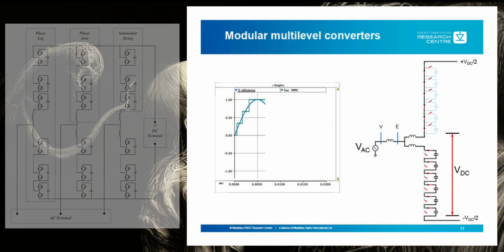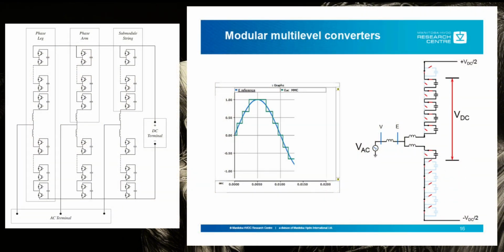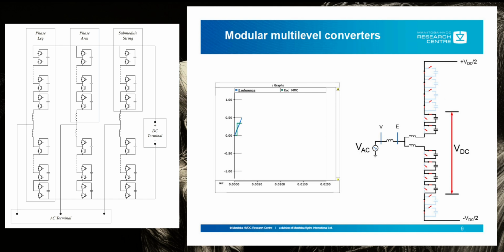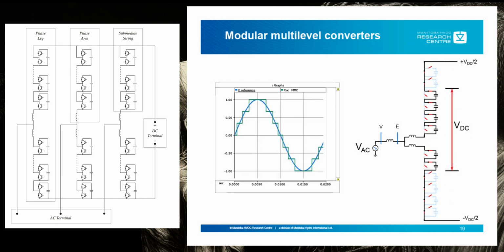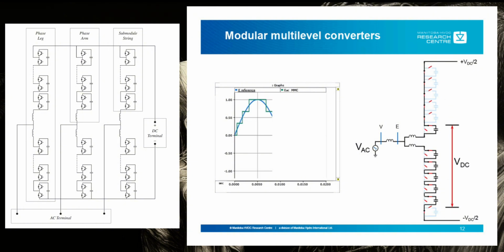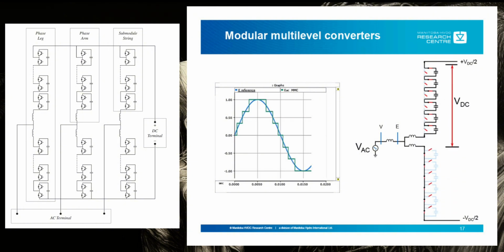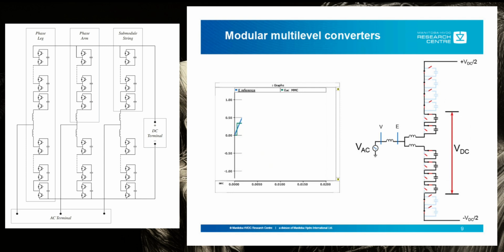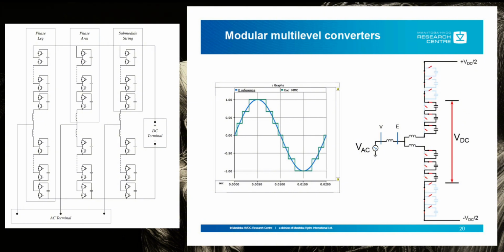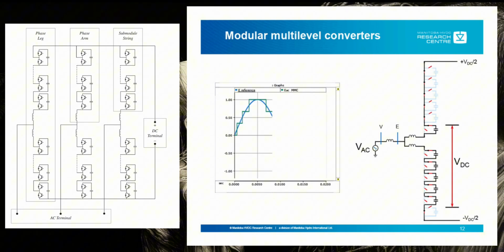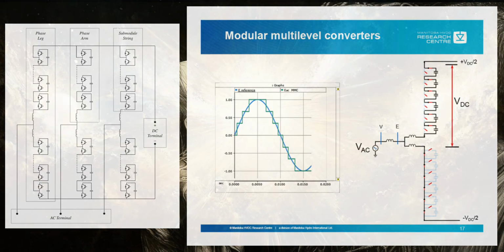While several converter topologies exist for voltage source converters, the modular multi-level converter, MMC, is what is used for utility-scale HVDC transmission. The MMC utilizes a string of IGBT cells in series to create the converter switching arms. The MMC will have individual phase legs to convert DC into three-phase AC. Each leg will have upper and lower switching arms to control the voltage polarity. Each arm is composed of a string of cells. Each cell will be a half-bridge or full-bridge IGBT configuration.